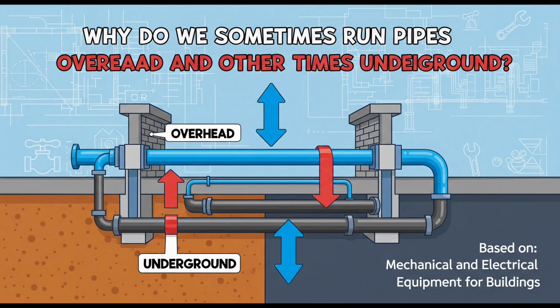Okay, now it's not just liquids and wires and pipes. Air flows through them too. Yeah. Tell us about things like earth tubes and underfloor air supply. How do they fit into this overhead, underground, within-structure picture? Earth tubes are a really neat example of using underground piping for essentially passive climate control. It leverages the stable temperature of the earth a few feet down. They're basically just long pipes buried underground. A fan pulls outdoor air through these pipes. As the air travels through, the surrounding earth naturally cools it down in the summer or warms it up a bit in the winter before it even enters the building's main HVAC system. Wow, so literally using underground pipes for a kind of natural pre-air conditioning and preheating. Exactly that. It's a low-energy strategy.